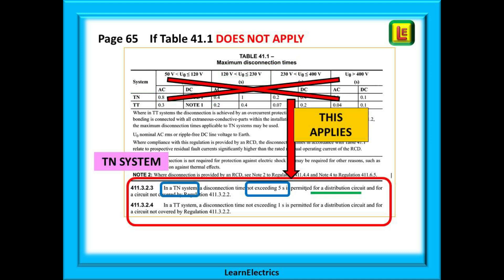If table 41.1 does not apply, what do we do? Just below the table are two important regulations and they do come up as exam questions. 411.3.2.3 tells us that if table 41.1 is not applicable or if it is a distribution system, then for a TN system we allow a disconnection time of 5 seconds.